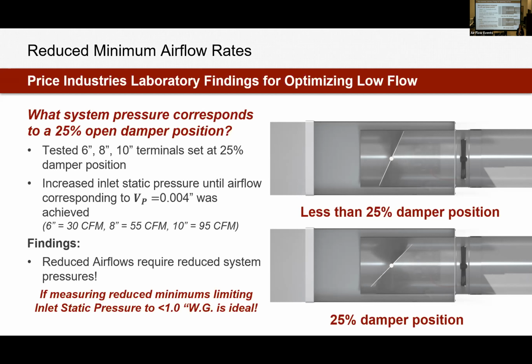Well, we might start seeing more units with fan arrays, so that you can not just turn one single fan down with a VFD, but you might see multiple fans within air handling units with multiple VFDs so that we can achieve very, very, very low airflows. And that'll be coming to Wisconsin hopefully soon, where we start to see 62.1 and more of these aggressive energy saving methods. So fan arrays, I can say, are becoming huge. Oh, wow. You tripped into the conversation. That's right.